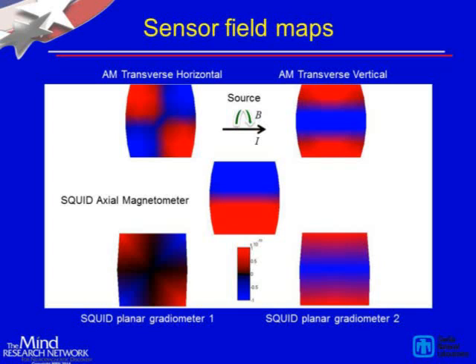If you look at the horizontal and vertical components measured by the atomic magnetometers, they actually compare very well to the planar gradiometers used in the SQUID system. If you look at the field maps for the horizontal field component, that compares pretty well to the planar gradiometer in the horizontal direction. And if you look at the vertical atomic magnetometer component, that corresponds with the vertical planar gradiometer in the SQUID system. So there's a nice correspondence between the two systems, if you're used to looking at field maps.